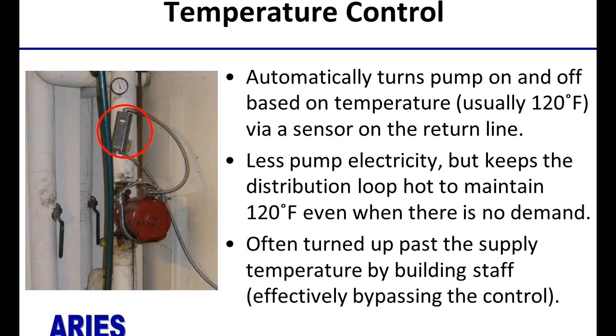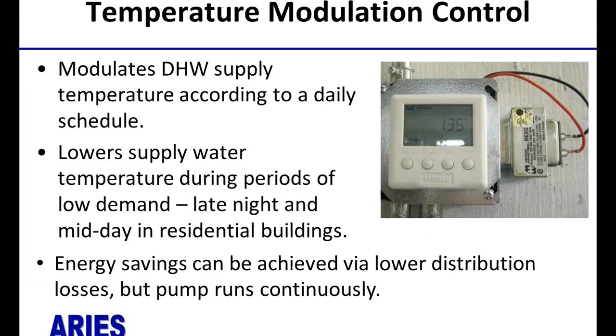Temperature control is another form of recirculating pump control, and it automatically turns the pump on and off based on a temperature set point, usually around 120 degrees, with a sensor on the return line. So this will use less pump electricity because it turns the pump off, but it won't do much to reduce the radiative losses from the pipes because the pipe temperature will remain at 120 or whatever the set point is.